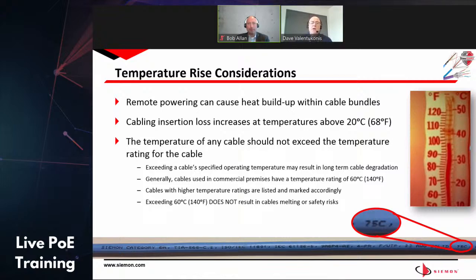So we want to make sure that typically you don't exceed cabling above 60 degrees C, which is about 140 degrees Fahrenheit. And what you're seeing to address that is that's what typically cables are rated to, but you're seeing more constructions come out now that have higher jacket ratings, for example 75 degrees C, to address specifically this heat buildup.